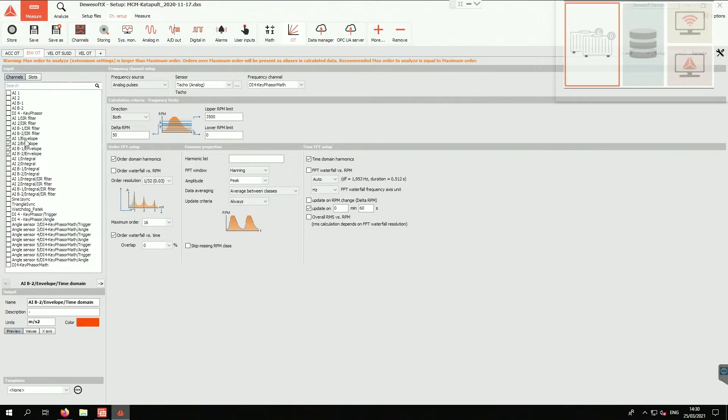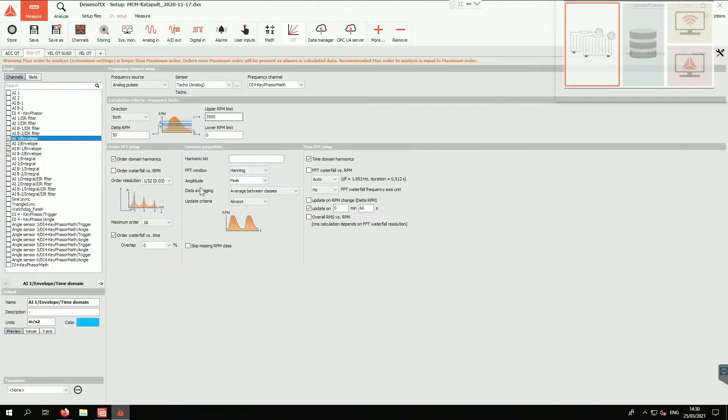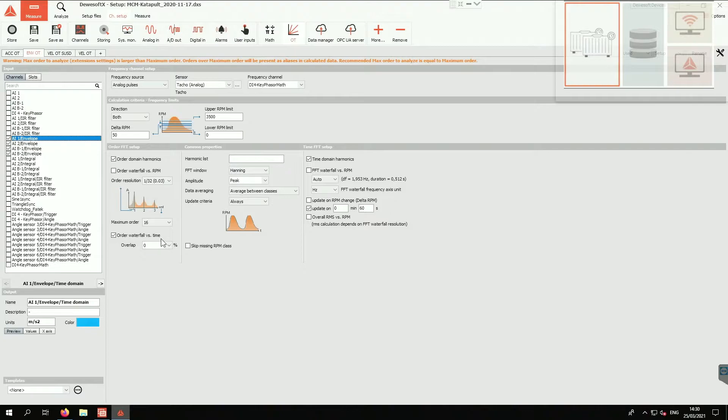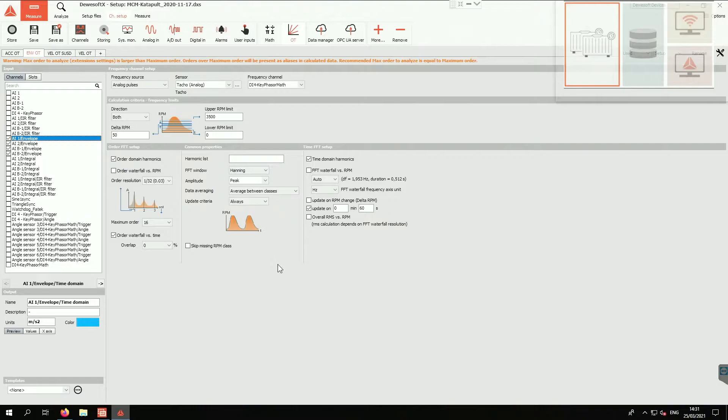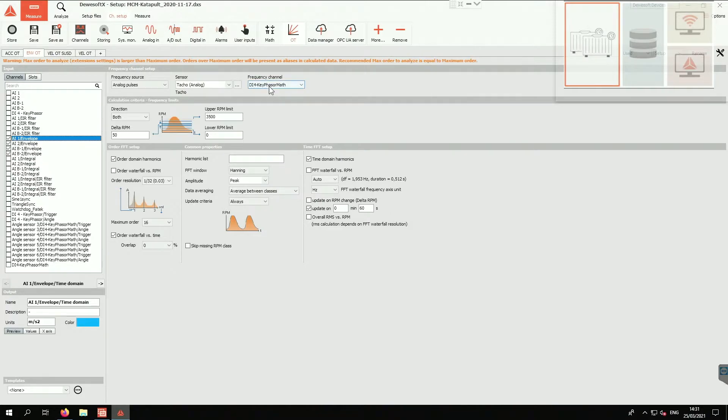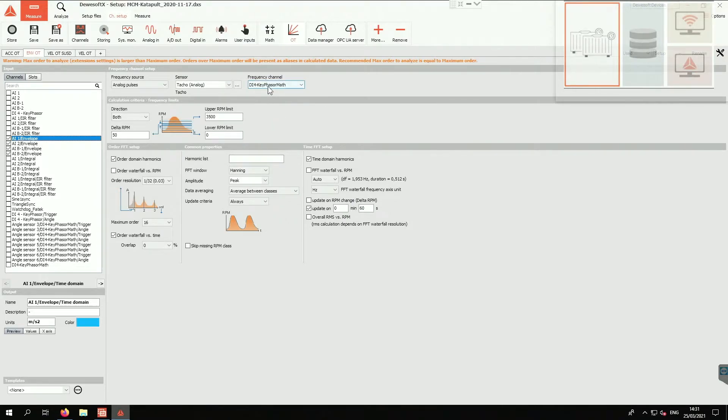We have the envelope signals as you can see as the inputs to the order tracking module, and we are focusing of course on the order waterfall versus time, so we will have time updates of the order or the waterfall basically. We have the keyphasor channel, so we have a digital input that measures pulses from a tachometer from the motor. This is our phase reference, actually our RPM reference.